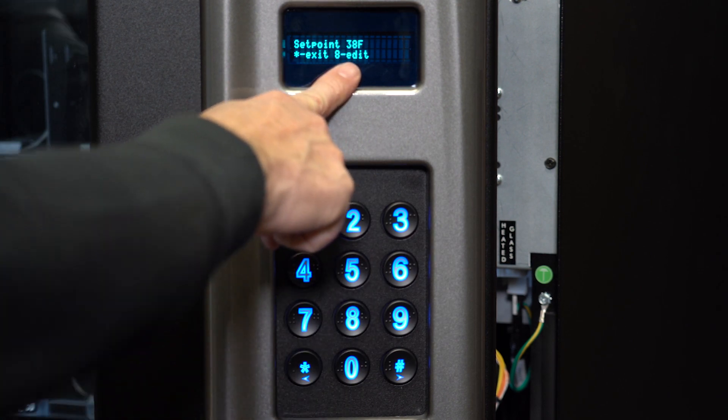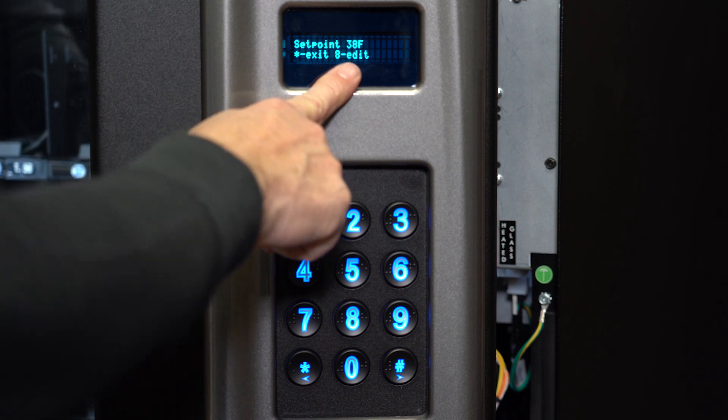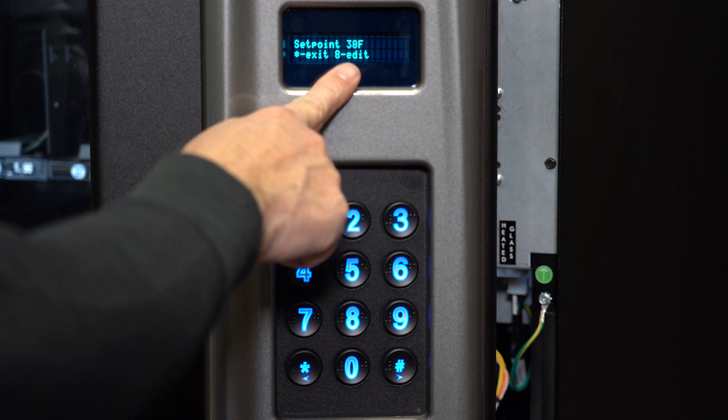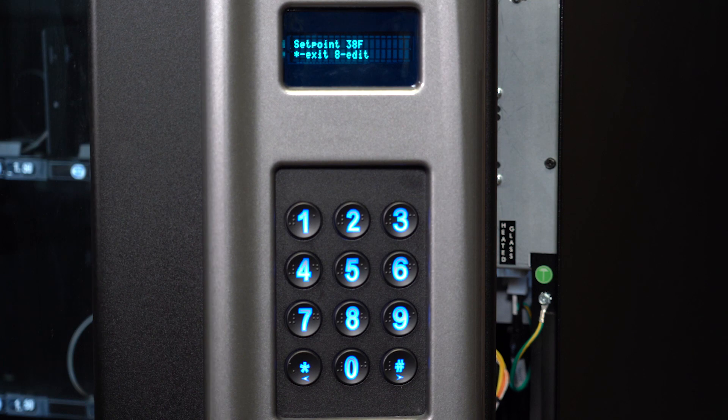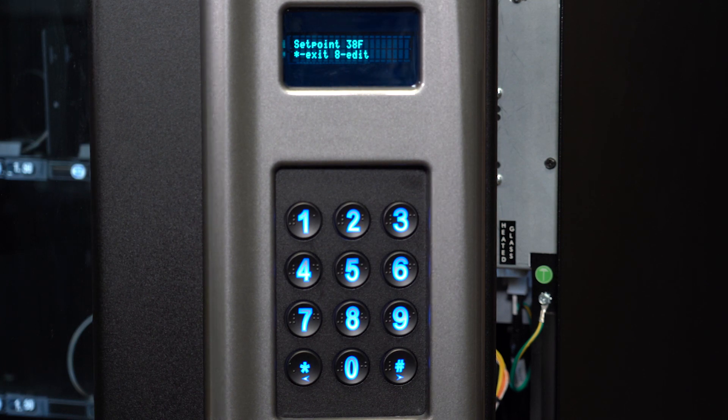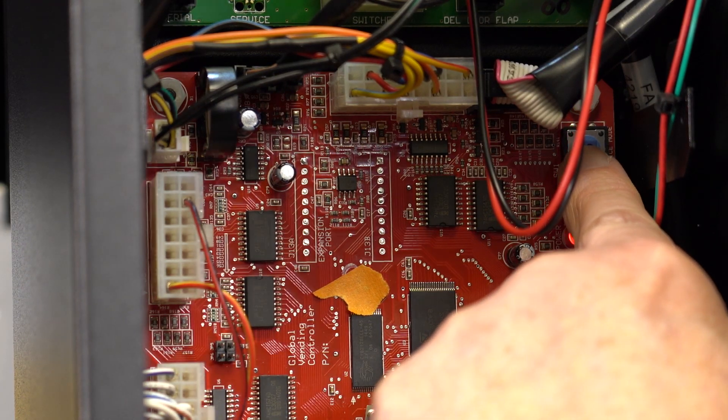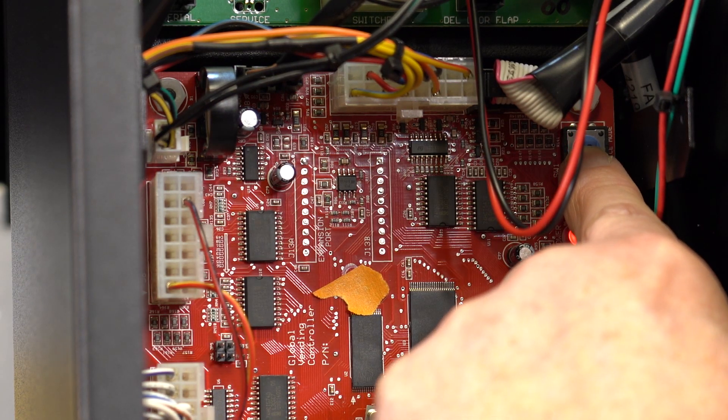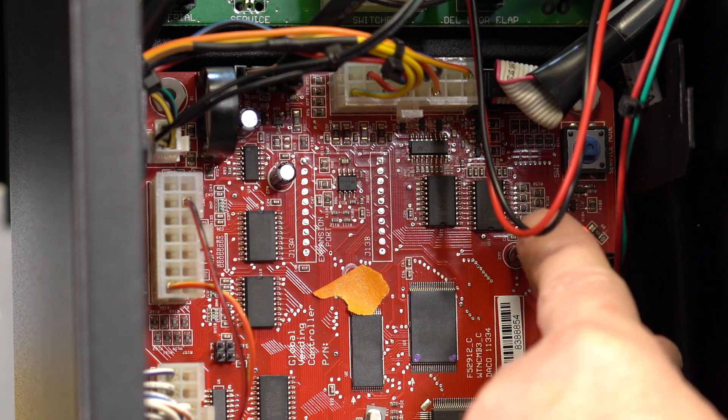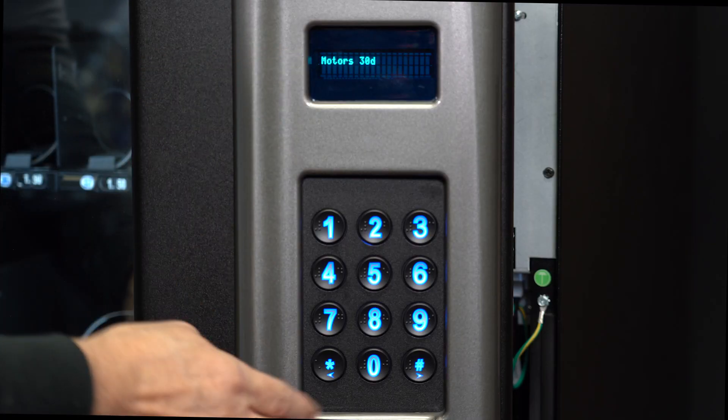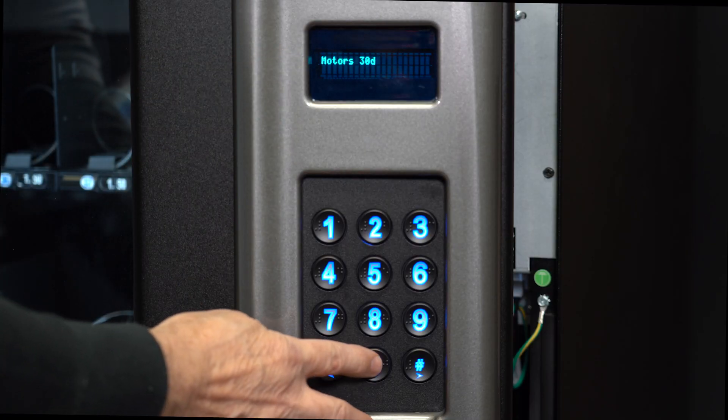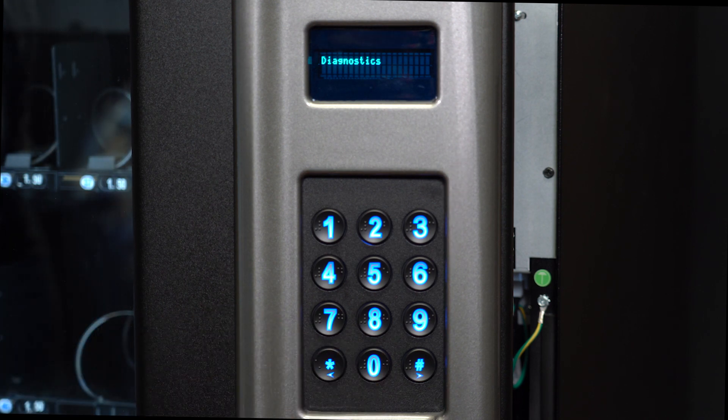If the machine is still not cooling, make sure that the fan and the compressor are working. You can try forcing them to come on in the diagnostics portion of the machine's programming. To do this, first put the machine in service mode by pressing this button on the control panel. When in service mode, press 0 to go to the diagnostics menu.